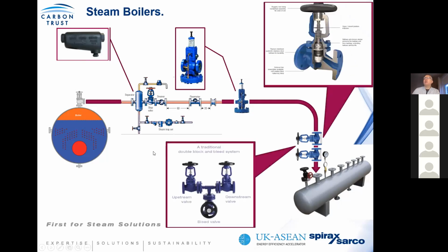You should also be looking at best practice, because from our experience, what we have found is that a lot of sites are struggling to do maintenance because they can't take down plant with a level of safety to ensure that maintenance craft can work on additional plant without cause for pressurization or steam leakage. So it's best practice to put in what we call double block and bleed, using a high quality valve with this kind of configuration here. And with this configuration, the whole idea is that you have dual isolation, one isolating the boiler, two isolating the distribution header, and the bleed valve, which you would fully open. So if there was any leakage from either system, it would leak to a safe discharge point. In other words, you could totally depressurize a boiler while still maintaining a steam distribution system at pressure from additional boilers.